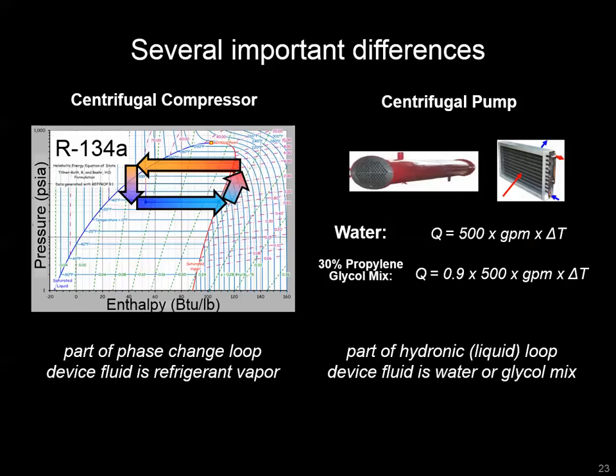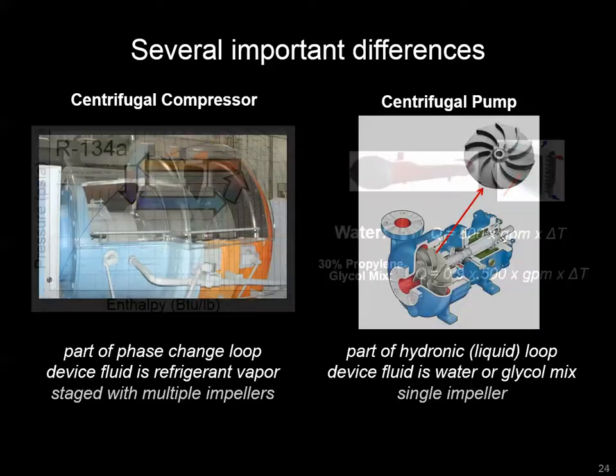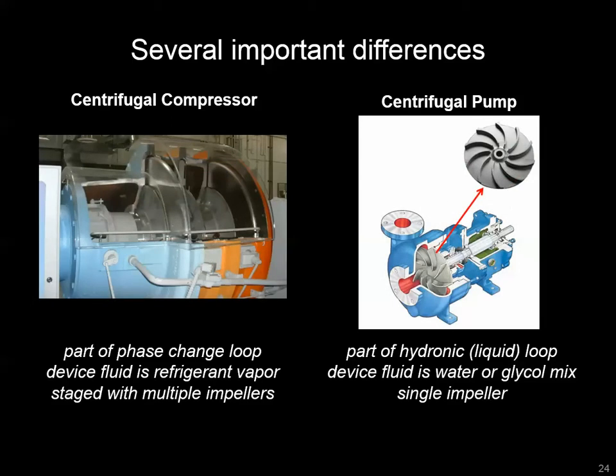The fluid in a compressor is refrigerant, while in a pump it's going to be some type of treated water — possibly with corrosion inhibitors, and if freezing conditions are expected, a percentage of glycol. The heat transfer equation we use with water — q equals 500 times the water flow in GPM times the delta-T in degrees Fahrenheit — will be modified somewhat depending on the amount of glycol used, since glycol has different heat transfer characteristics that may derate your system capacity.